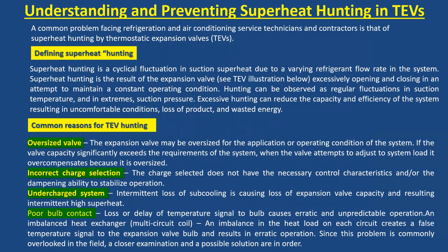Hunting of the thermostatic expansion valve refers to cyclic fluctuation in suction superheat due to varying refrigeration load. It causes continuous, excessive opening and closing of the expansion valve, which reduces the capacity and efficiency of the system. Hunting is a common problem faced by refrigeration and air conditioning service technicians.